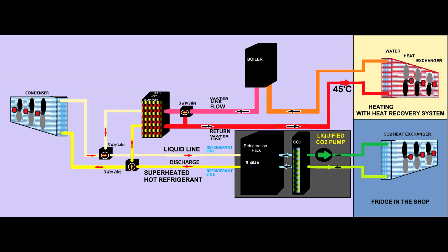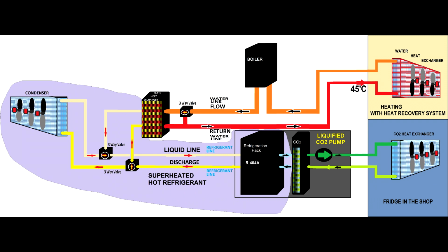Now let's see how this particular system is designed. You will have the primary refrigeration system section, the carbon dioxide section, and the water section. What you'll see here is the refrigeration section. You have a compressor, the condenser, the TX valve, and also this plate heat exchanger, which acts like a condenser. So that's the heat recovery module.